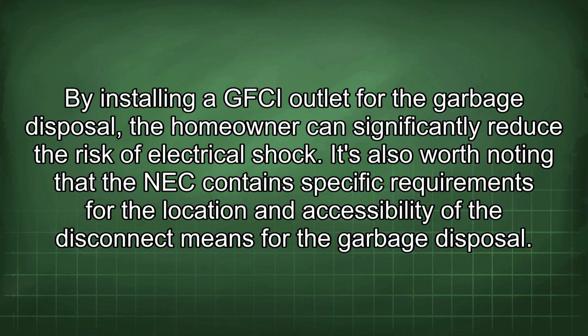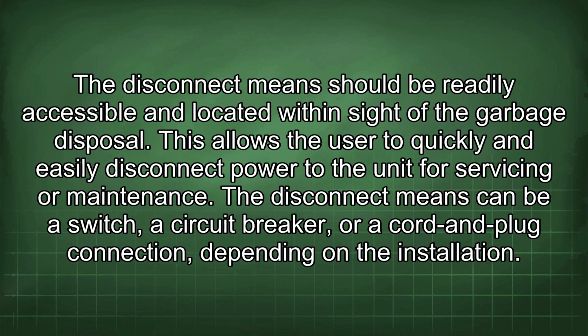It's also worth noting that the NEC contains specific requirements for the location and accessibility of the disconnect means for the garbage disposal. The disconnect means should be readily accessible and located within sight of the garbage disposal. This allows the user to quickly and easily disconnect power to the unit for servicing or maintenance. The disconnect means can be a switch, a circuit breaker, or a cord and plug connection depending on the installation.